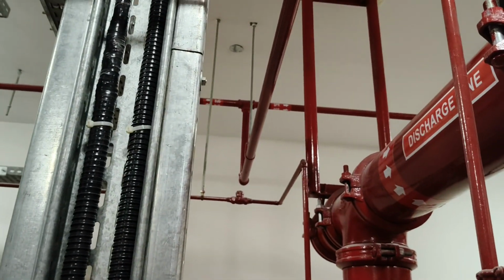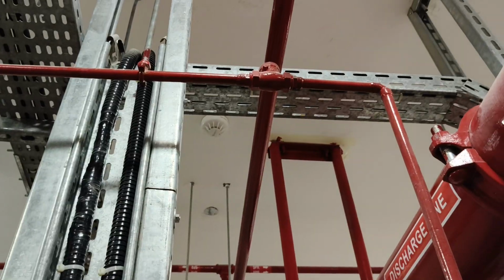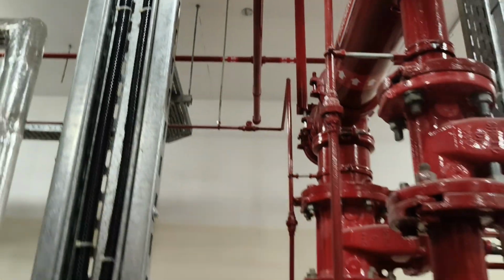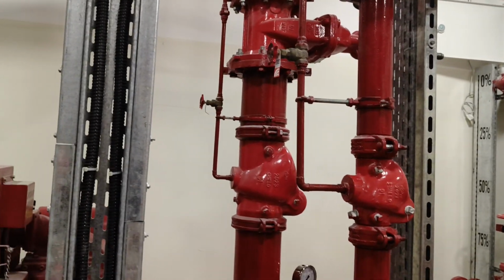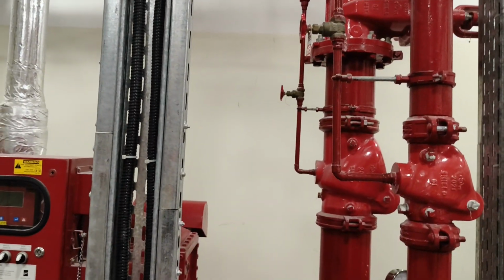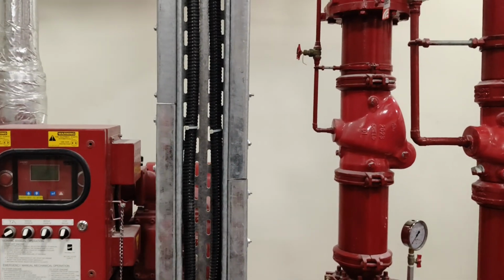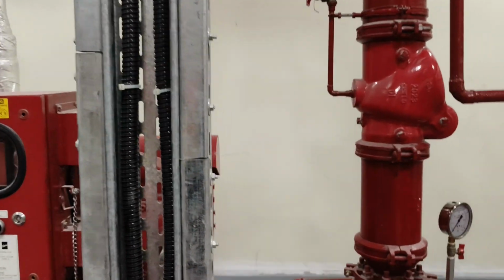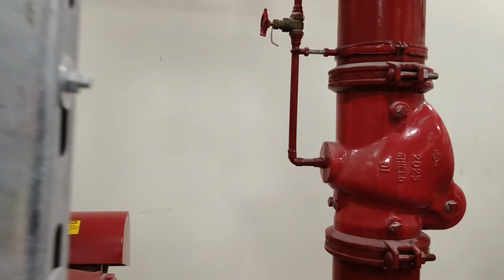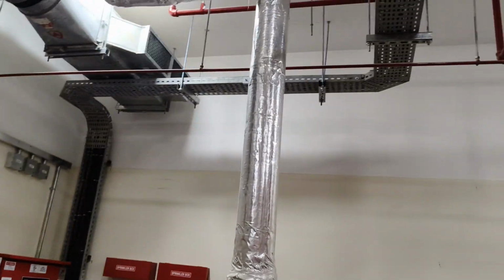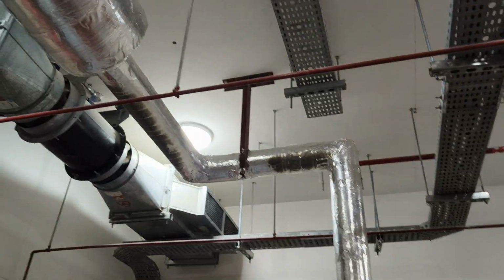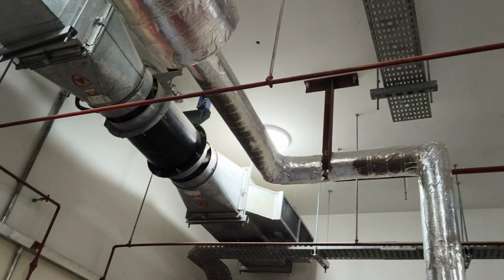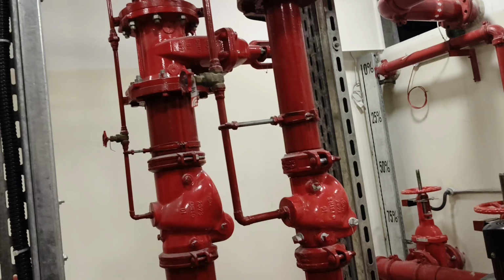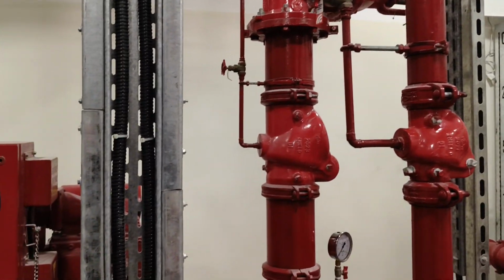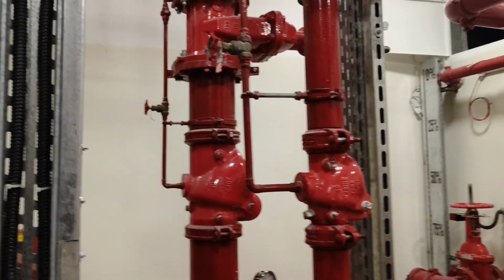And you can see this side also. It's also the same, all right? So all the systems have a sensing line going in the opposite direction, and there is a 4mm hole drilled in the check valve. Okay, so this is it for the jockey, and that is it also for the diesel. And this also is connected directly to the diesel. So you could see that everything that we are doing here has been made at a level of height, so there will not be any disturbance. On most sites you will see the sensing lines on the floor, and because it's copper, people tend to step on it and it starts to get broken.